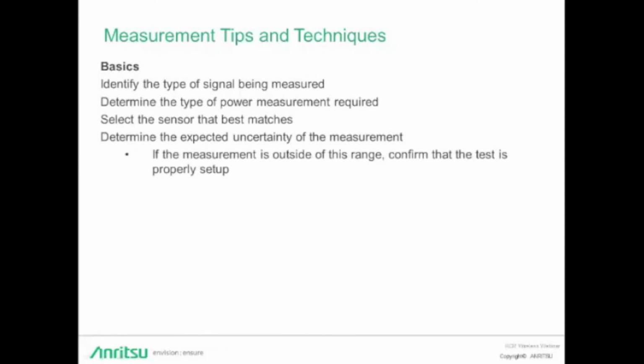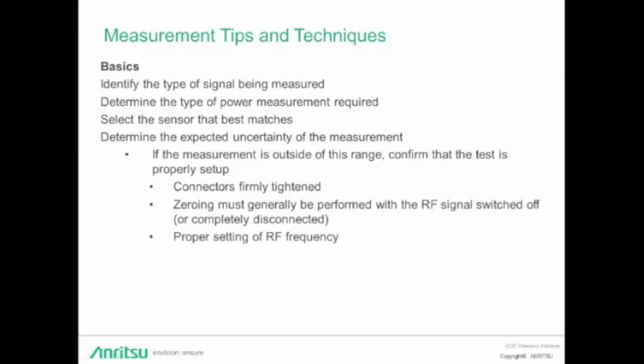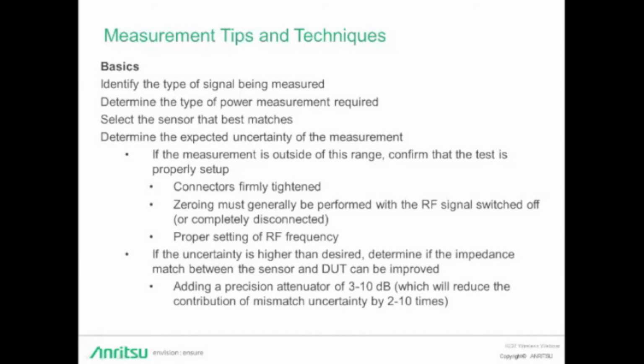Now, if the measurement is outside of the range of the expected uncertainty, you want to confirm that your test is properly set up. Are your connectors firmly tightened? Zeroing must generally be performed with the RF signal switched off or completely disconnected. Proper settings, have you set the RF frequency properly? If uncertainty is higher than desired, determine if the impedance match between the sensor and the DUT can be improved. Again, like we mentioned, possibly adding a 3 to 10 dB attenuator, which could reduce the contribution of mismatch by 2 to 10 times.